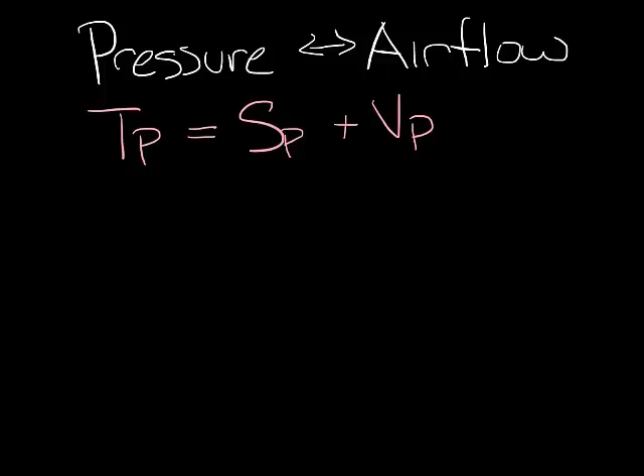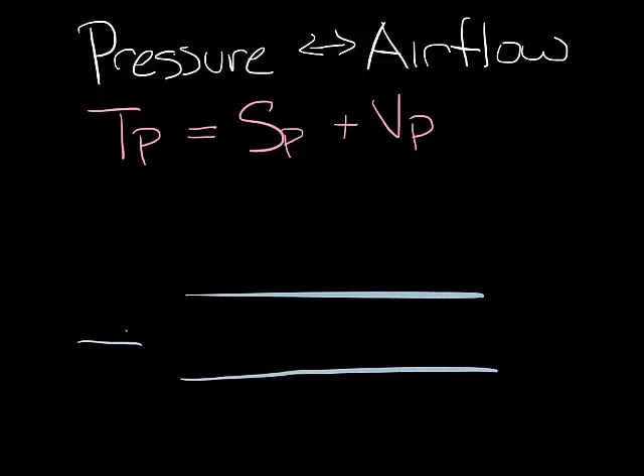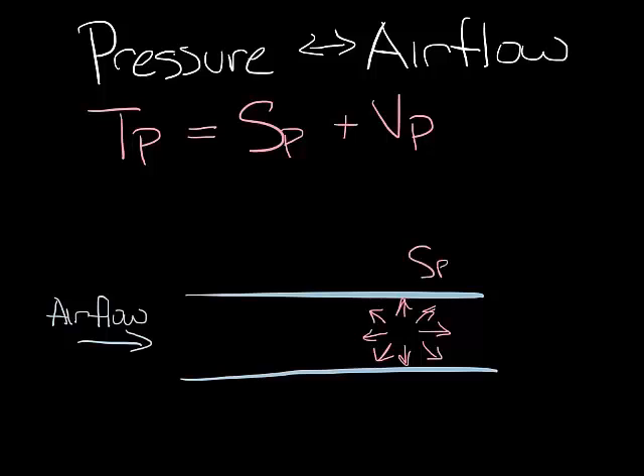When air moves through ductwork, there are two components of pressure going on: static pressure, which is exerted in all directions, and velocity pressure, which is only exerted in the direction of air flow. The sum of these is total pressure.